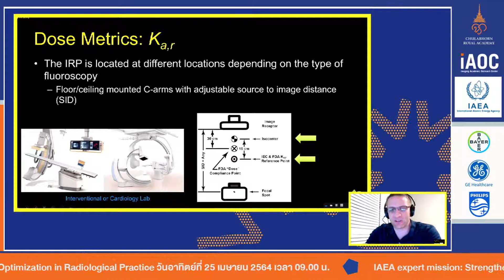If you go 15 centimeters from the isocenter towards the X-ray tube, that is the international reference point. It's always 15 centimeters towards the X-ray tube from the isocenter. Now, why is that?